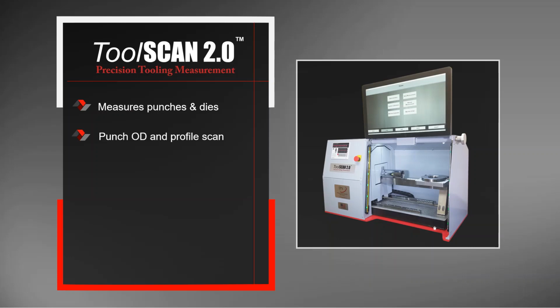On the punch, it will measure the outer diameter as well as perform a profile scan of the step of the punch. By measuring the outer diameter, it will report three values: the major diameter, the step, as well as the taper on the punch.